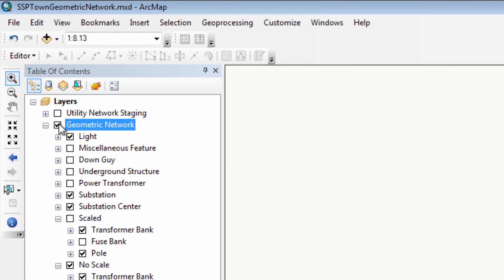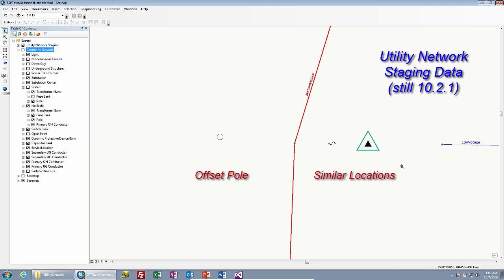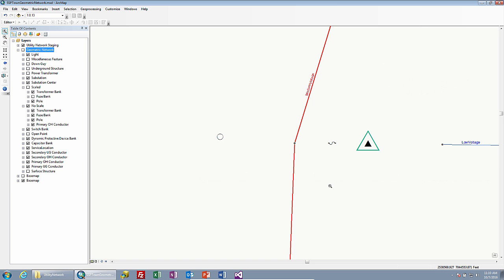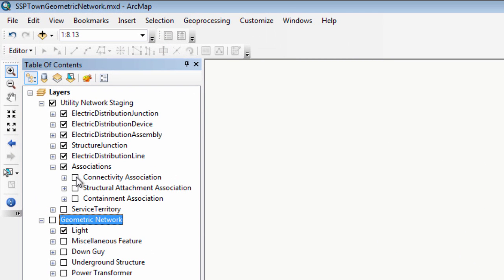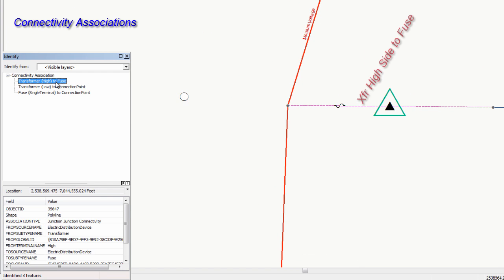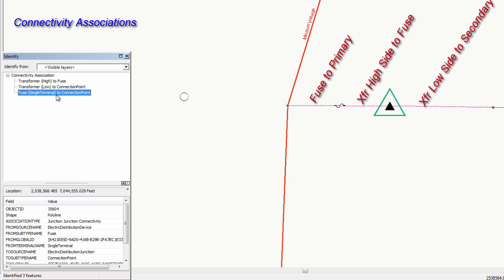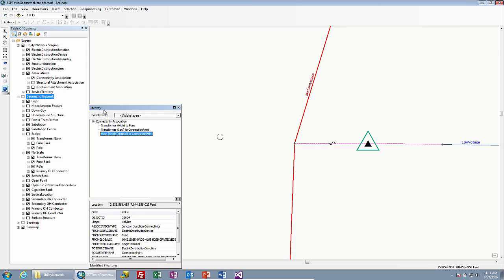Let's see how that translated into the utility network model. Turning on these layers, you'll see a very similar model with several different things. In this view, we're seeing that the pole has been offset, the fuse and transformer are still in relatively the same locations, and the secondary has been offset as well, with no lines drawn within the components. However, we are able to still establish connectivity. Opening up our utility network staging database and showing connectivity associations, we have the transformer high side connected to the fuse, the transformer low side connected to the connection point outbound on the secondary, and a fuse which is connected single terminal over to the connection point — that's our tap point off of the medium voltage line.